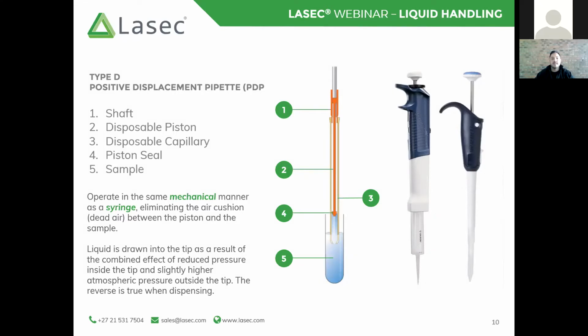So the principle is relatively the same in terms of using a piston to aspirate and dispense liquids and to transfer those micro volumes of liquids. However, the positioning of the piston is very different to the air displacement pipette. So in order to alleviate any of the shortcomings with air displacement pipettes, we now use a physical plunger. We've removed that air pocket or that air cushion, thereby removing any of those elastic properties of that air mass, and we have replaced it with a physical plunger.